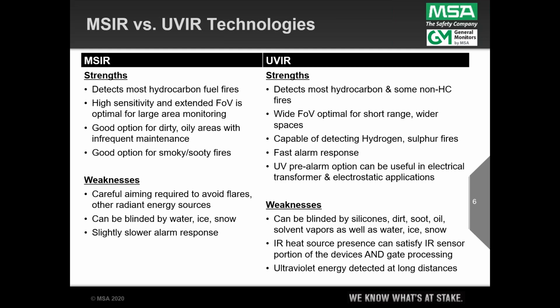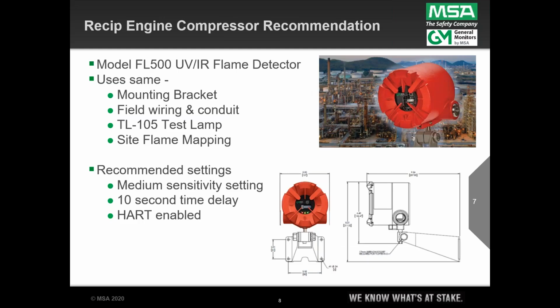And likewise, if you have welding in the field of view, or IR, you have some heat, then it's a UV-only detector. So it just means that because of that more basic processing, if you have that energy, you're halfway to a fire alarm in an AND gate type of device. But the bottom line is that they're both very world-class, both provide world-class performance. But in some applications where you don't need that longer range capability, MSA is recommending the UVIR as a suitable and basically the optimal technology.